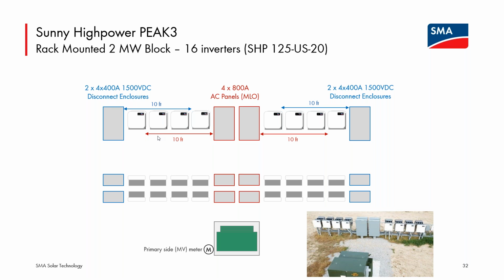Under 690.15, you may be required to have disconnecting means, both DC and AC, within 10 feet of the inverters. So having the ability to place these inverters very close to each other matters. All of the airflow in the inverters is from the back top down, so there is the ability to place them very close together, side to side. So you can have setups like this to large plant size, complying very easily with code and scaling up to very, very large blocks.